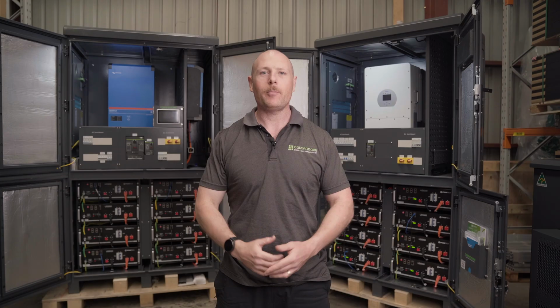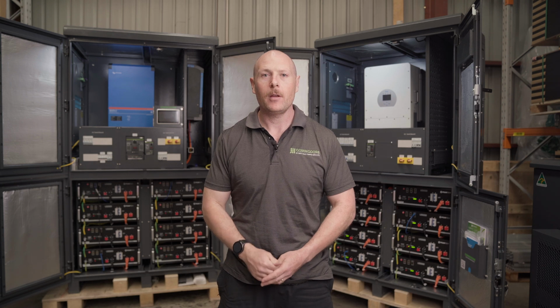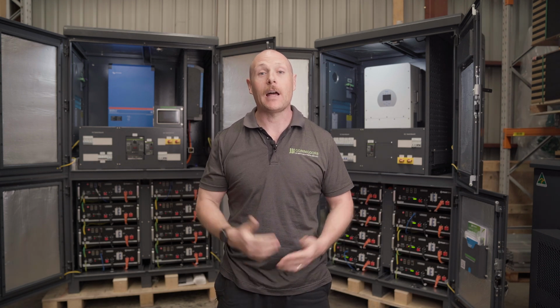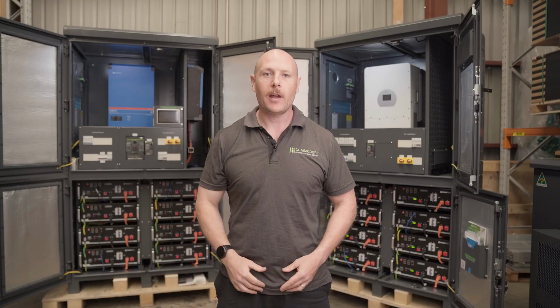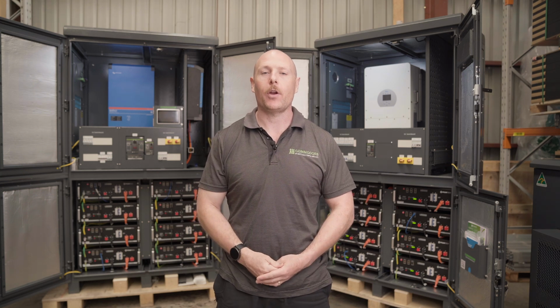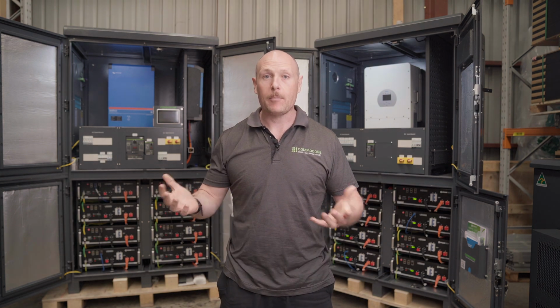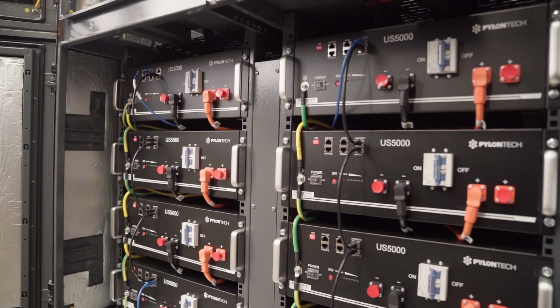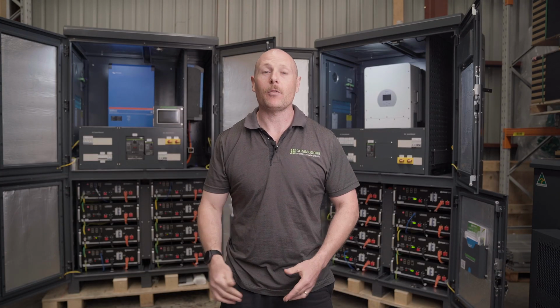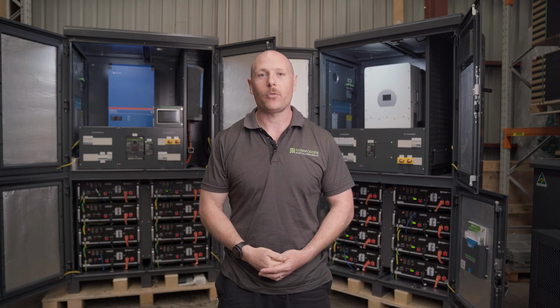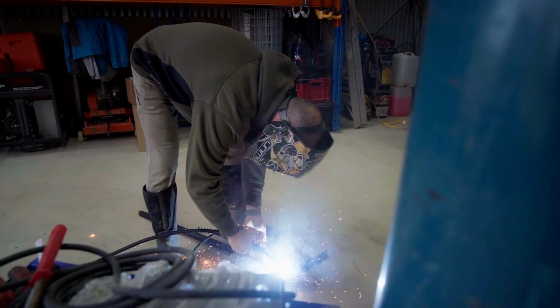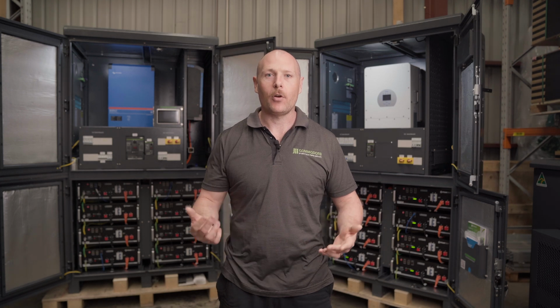The next size up is the Power Hub XL cabinet, which is most commonly found powering large family homes. This can take up to 15 kVA of inverter power. It has room for 8 batteries, which is 40 kilowatt hours of battery storage, and can take up to 14 kilowatt of DC coupled solar. It's ideal for properties with higher daily loads or multiple air conditioners and appliances.